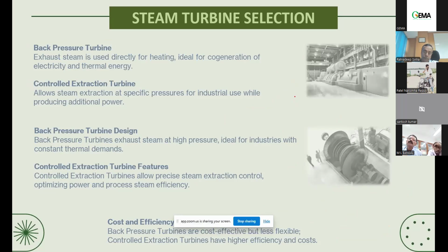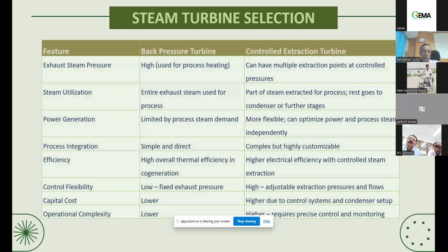So these are basically the features. Back pressure turbines are cost effective, but flexibility-wise this has a challenge. Control extraction turbine efficiency - the turbine front efficiency is higher, but overall efficiency of the system will be a little bit lower, and the cost will of course be higher. So this is just a comparison out of it.